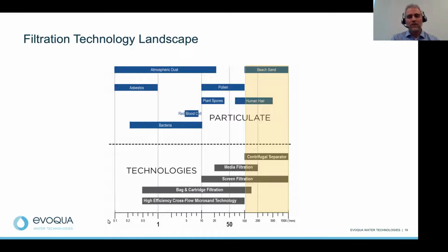Centrifugal separators or hydrocyclone separators, really, 100 micron nominal, I would say, depending upon the specific gravity and the type of particle, but it's a good average micron removal. When you compare that to various different particulates in a cooling system, you can find beach sand as an example, or even human hair. So it's really important to understand what the technology's capabilities are when you're choosing that type of technology for your solution.